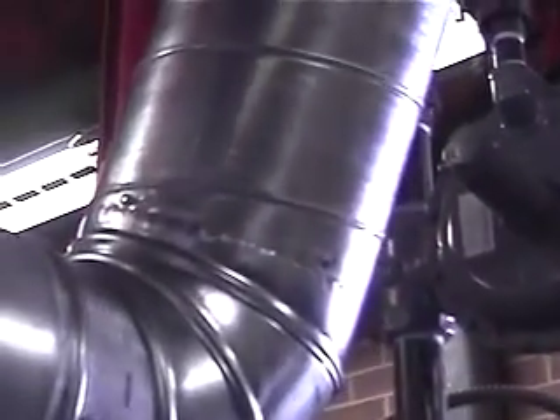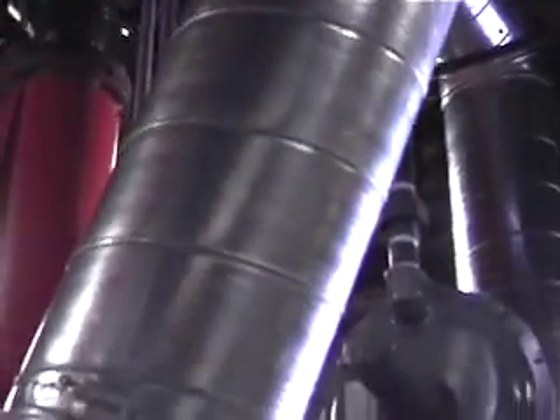Reduce the temperature settings as necessary. Check temperature. You've got your air inlet here, which is coming in. Does that come in from that parking area over there? That's where it pulls the air inlet. And then your flue gases go out at the top. So you're definitely in 2 different pressure zones. So like we talked about before, you will see a change in combustion. But this is where you're going to want to check.